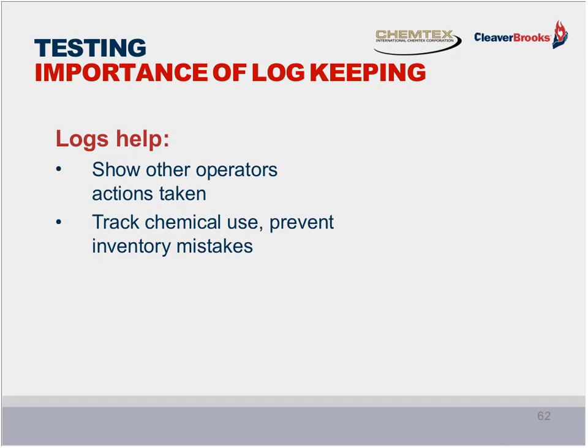And logs are critical because logs show operators other than yourself what actions have been taken. If you find the conductivity is high and you increase the surface blowdown, and the next operator comes on shift and finds that the conductivity is high and he increases the blowdown, pretty soon you've taken a major step where only a minor step was necessary. So logs are very important to document what actions are taken.